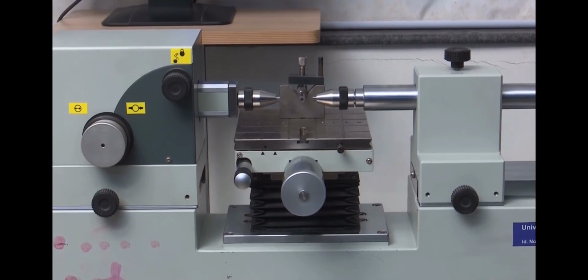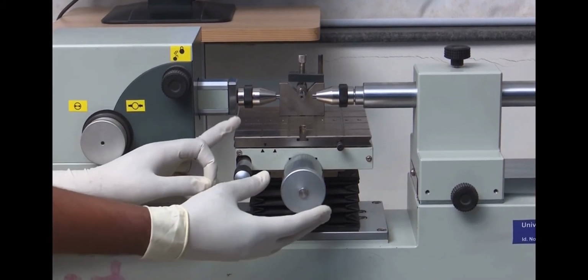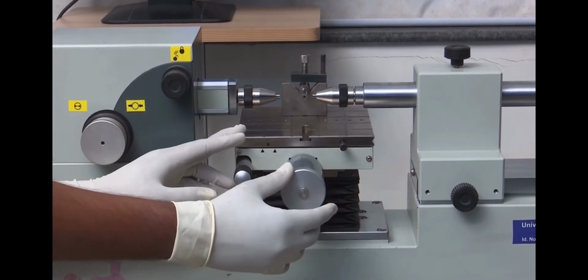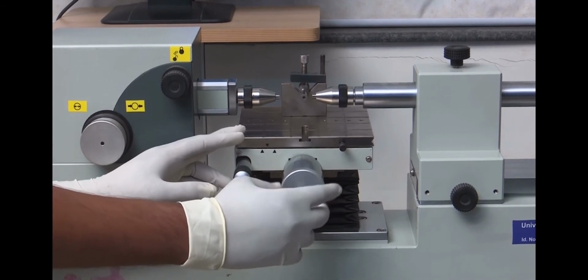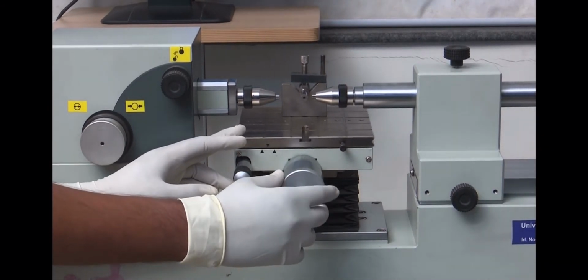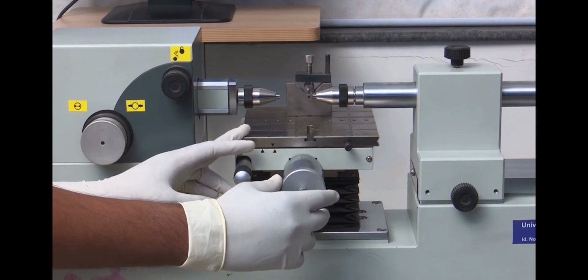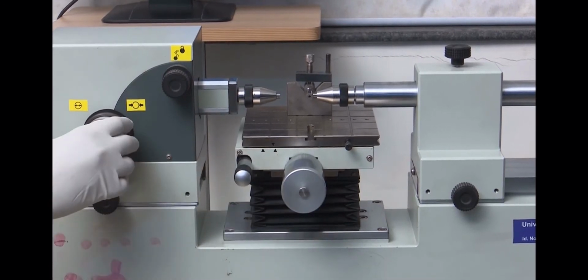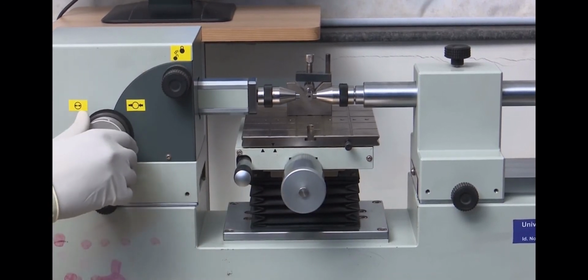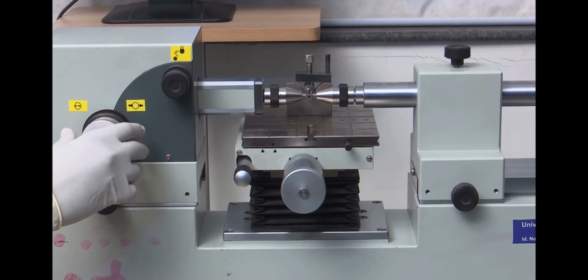Now bring plain plug gauge approximately at the center of table by rotating the table screw. Adjust the machine stroke by moving tailstock spindle. Now I am applying measuring pressure by rotating constant pressure assembly in clockwise direction and then I lock the pressure.